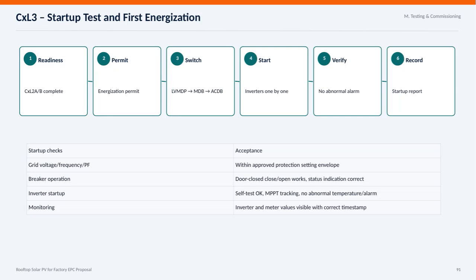This slide outlines the critical steps involved in the startup test and first energization for the rooftop solar PV system. First, we ensure readiness by completing the CXL2AB phase, confirming all preliminary checks are done. Next, we secure the necessary energization permit to proceed safely. Then we switch the power flow through the LVMDP to MDB and finally to the ACDB, establishing the correct electrical path. We start the inverters one by one, carefully monitoring each one to avoid any issues. We verify that no abnormal alarms occur during startup, ensuring system stability. Finally, we document everything in a detailed startup report.